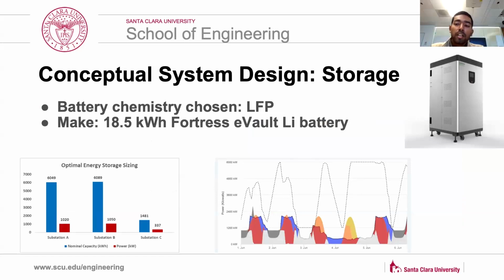So moving on to the storage, an eVault battery of 18.5 kilowatt hour nominal capacity was chosen for a turnkey solution. We chose the lithium iron phosphate chemistry for higher durability, efficiency, greater safety, and faster charging as compared to lead acid batteries. This particular one has an incredible rated life cycle of 6,000 compared to the average for lithium ion batteries of 3,500, and a high nominal voltage of 51.2 VDC.